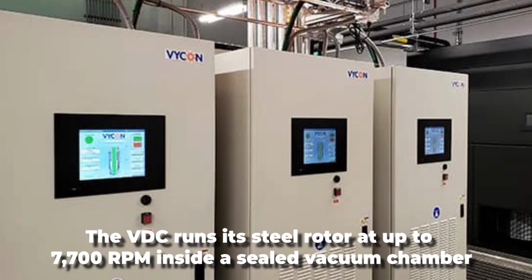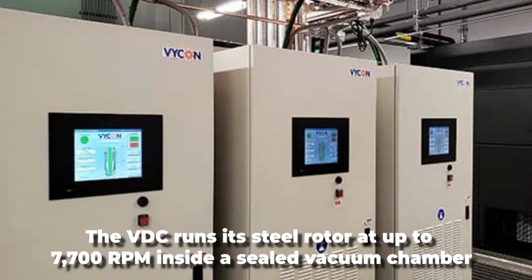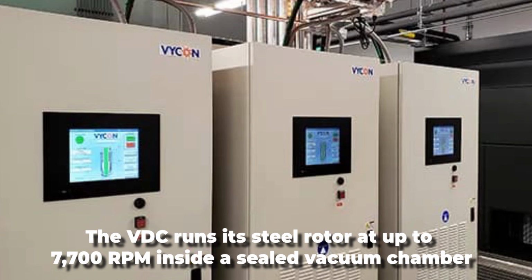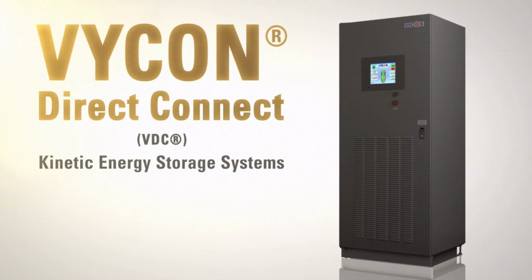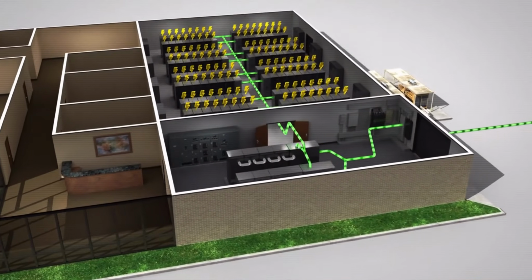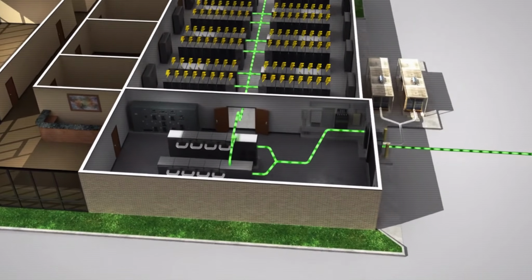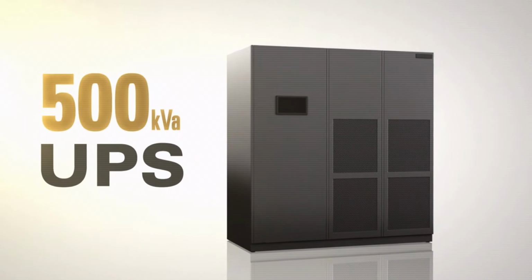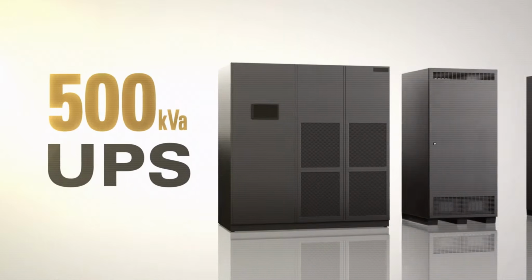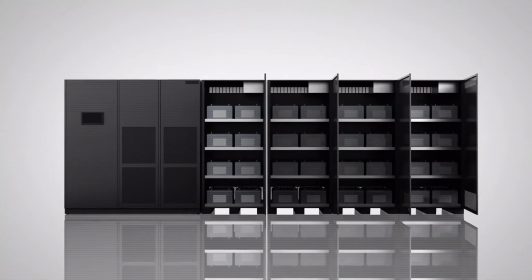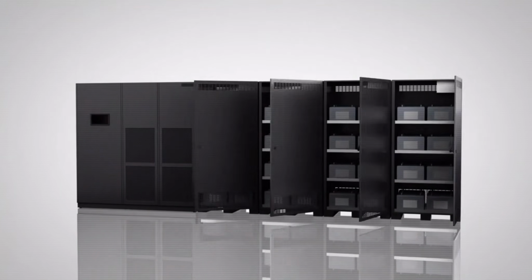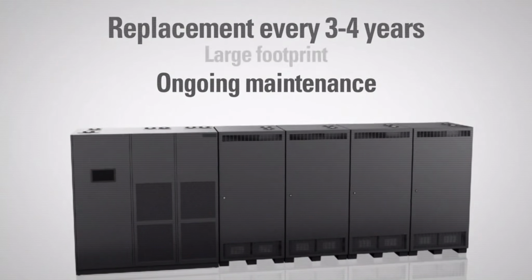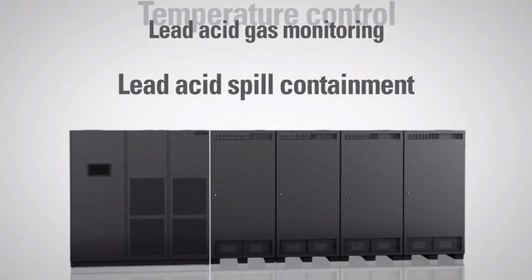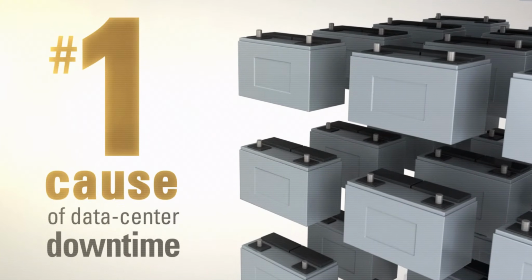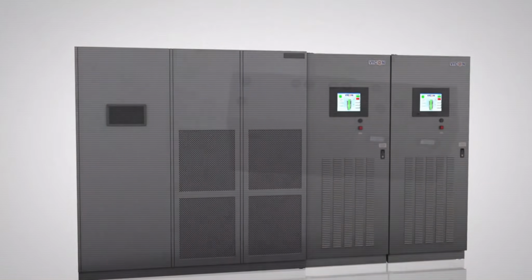The VDC runs its steel rotor at up to 7,700 revolutions per minute inside a sealed vacuum chamber, using magnetic bearings that touch nothing and therefore wear down nothing. I wanted to stress test this one specifically, so I modeled it against a 250 kilowatt UPS load pulled from a real manufacturing facility profile, heavy crane and motor start demand, the kind of load that spikes hard and fast and absolutely murders a standard battery UPS through repeated deep cycling. Simulated over a 90-day load cycle, the VDC handled every single spike event without a single projected maintenance intervention.